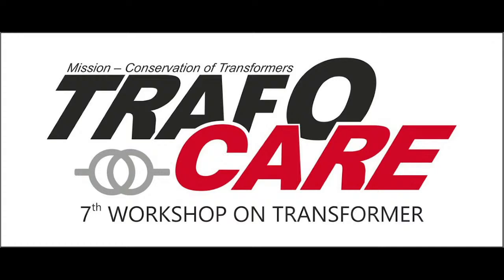Actually, I'm not going to reply directly, but this book has already mentioned the SOP for this - please go through that. Still, as he's raising the point, what are the reasons for using an external tank versus the same tank? What is the purpose of your oil filtration - is it a routine maintenance practice, or are you trying to dry out the transformer or remove some sludging? If it's routine oil filtration with no fault found, you can do it through the main tank.